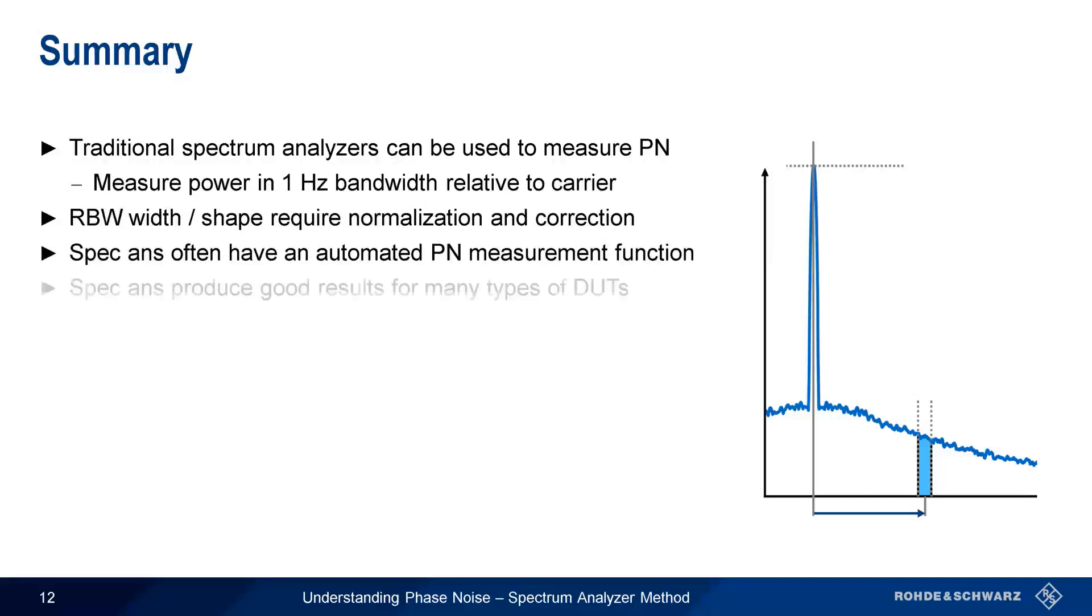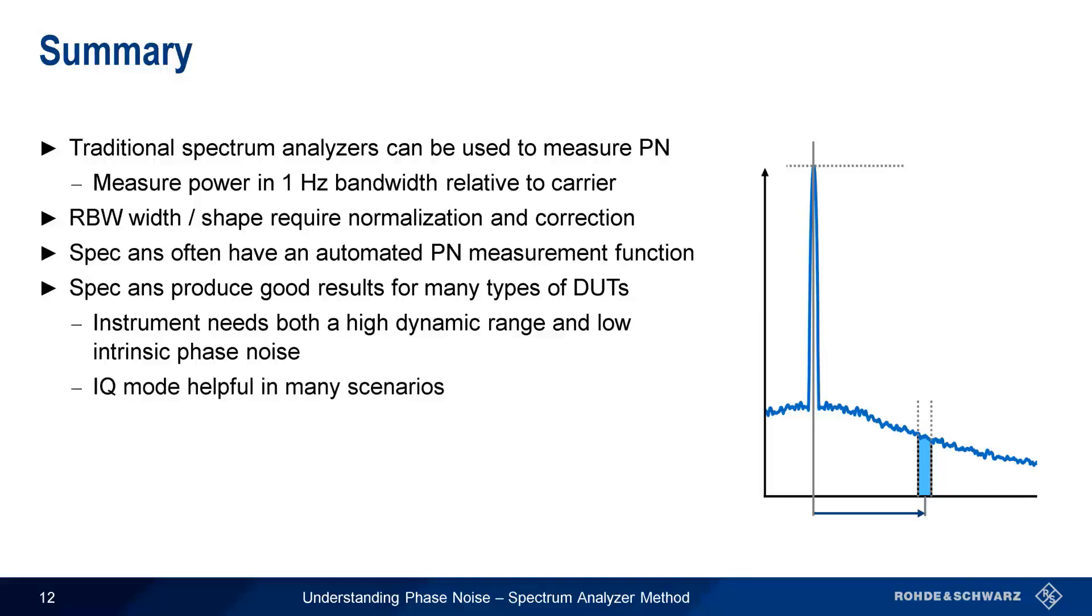For many types of DUTs, spectrum analyzers can provide good phase noise measurement results, although the instrument should have a high dynamic range and low internal or intrinsic phase noise. In addition, the ability to measure phase noise using IQ data can be helpful in certain scenarios.